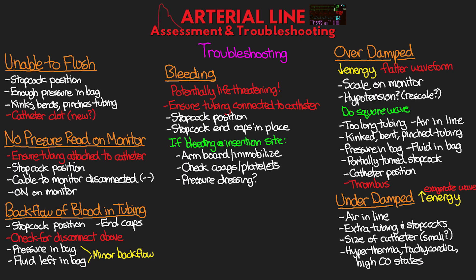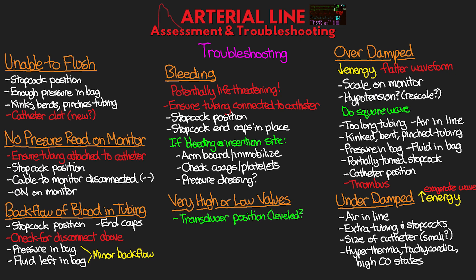Finally, if you notice very high or very low systolic and diastolic readings — especially suddenly — first check your transducer position and ensure it is leveled at the phlebostatic axis. If it is, re-zero the transducer and perform a square wave test to check damping. If all of that checks out and the over/underdamped troubleshooting is complete, then this is probably an accurate reading and needs to be treated as such.